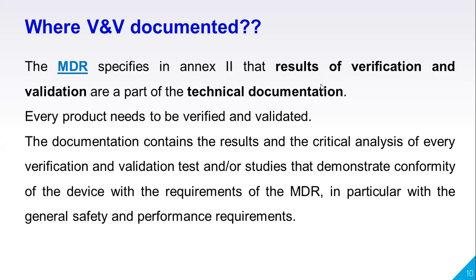So in order to clear the acceptance to release into the market, and in order to establish the safety as well as performance of this medical device as per intended use, the results of verification and validation must be included in the STED.